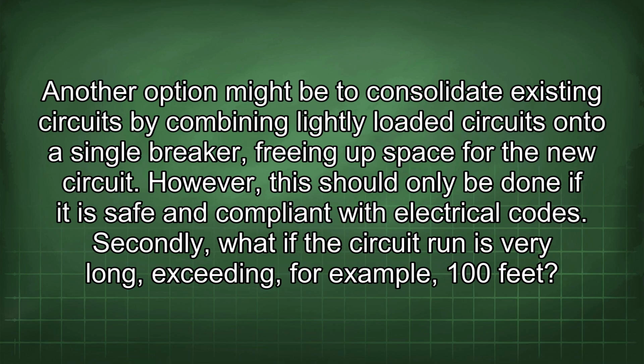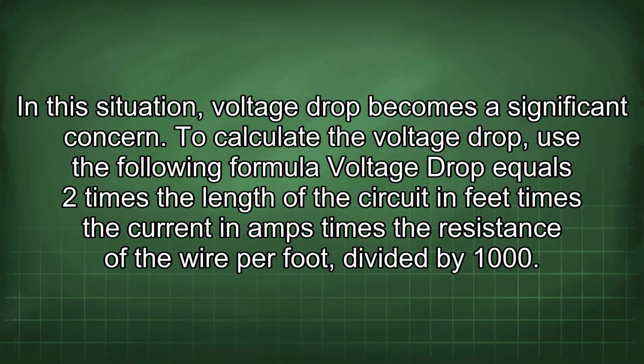Secondly, what if the circuit run is very long, exceeding, for example, 100 feet? In this situation, voltage drop becomes a significant concern. To calculate the voltage drop, use the following formula: voltage drop equals 2 times the length of the circuit in feet times the current in amps times the resistance of the wire per foot divided by 1000.